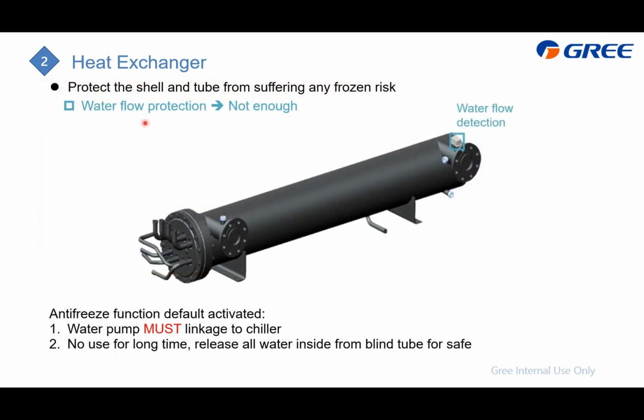And for this one, we have also considered the freezing protection, which means in cooling, as we need to cool down the water. If the refrigerant is very cold and makes the water lower than the freezing point, it may also make the system freeze, which may lead to damage. And on the system, we have these countermeasures, these solutions. First is the water flow protection, which is located here. There is a water flow switch to detect if there is not enough water flow, it will trigger the error.